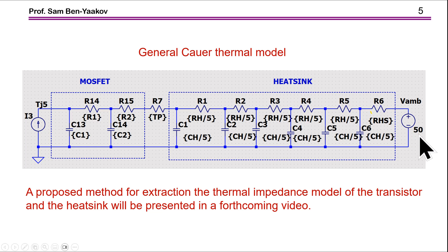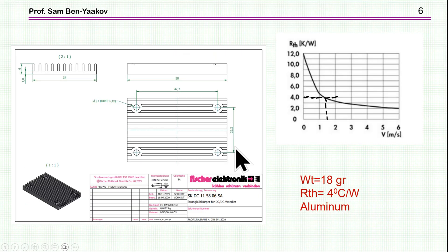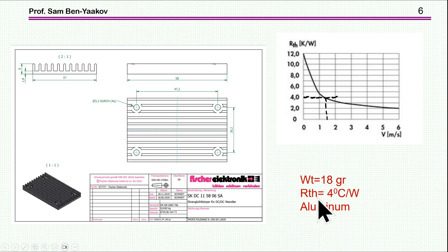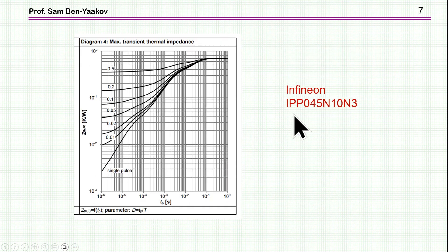I'm showing a 50°C ambient, and this will be the thermal power fed to the system. I'm going to demonstrate use of this model by considering a heatsink of about 60×60 mm, with an operating point of 4°C/W for a certain airflow. The weight of this heatsink is 18 grams, the thermal resistance is 4°C/W, and it is made of aluminum. For demonstration I'm using an Infineon power MOSFET.